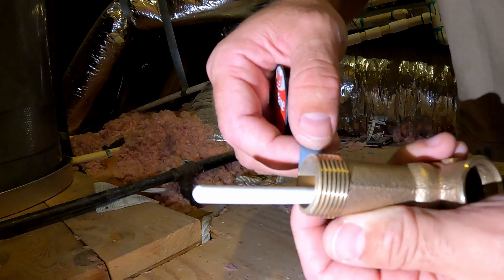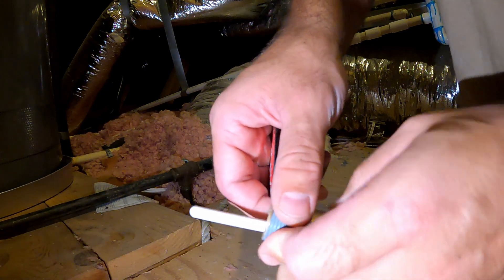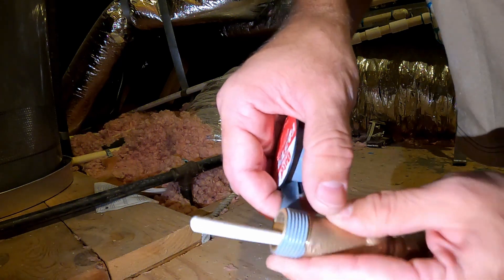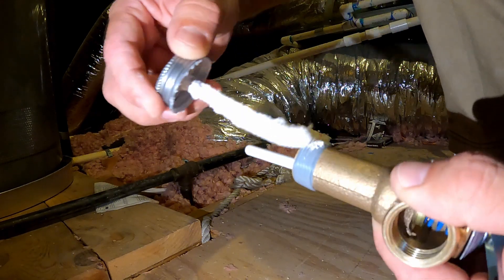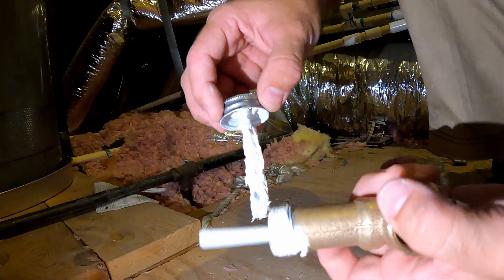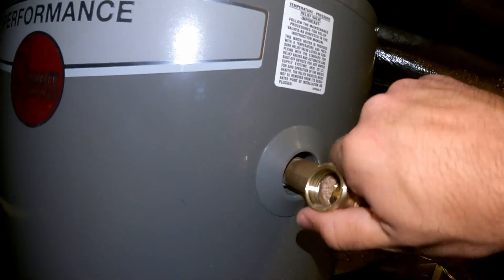All right, we apply Teflon tape, going clockwise. Apply two to three coats. Then put the thread sealant on top of it, spread it around, and make it nice and even all around. Start by putting it in with your bare hands so you make sure you're not going to cross-thread it.